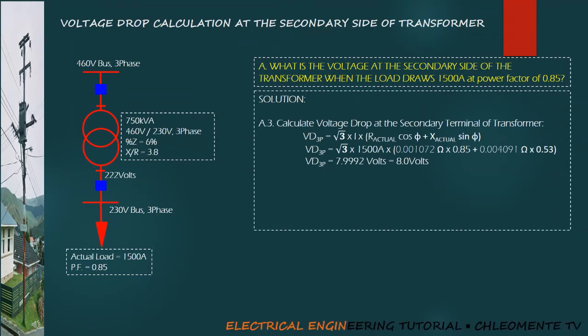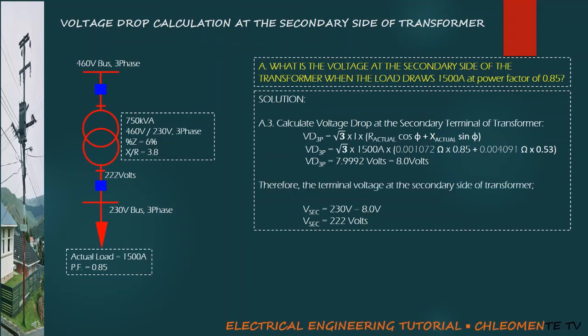Then using the voltage drop formula, voltage drop in 3 phase equals square root of 3 multiply by actual load current multiply by the sum of actual resistance cosine theta and actual reactance sine theta, which yields 7.9992 volts or 8 volts.